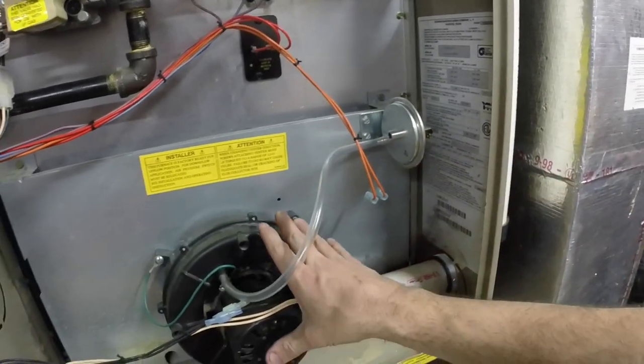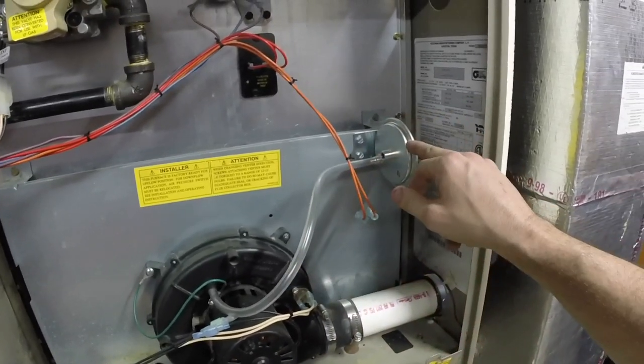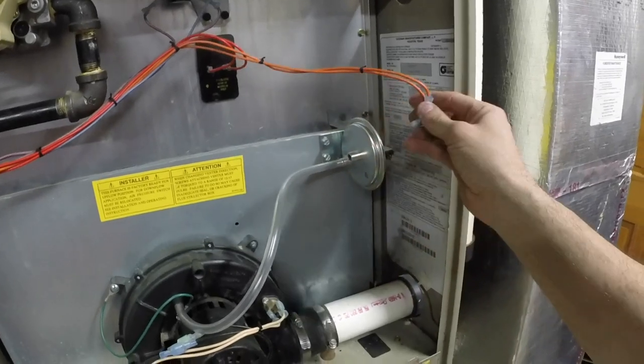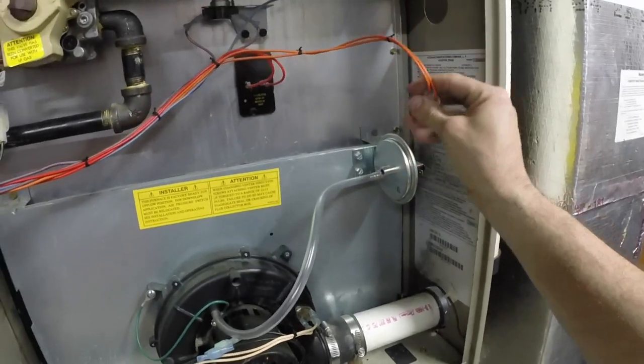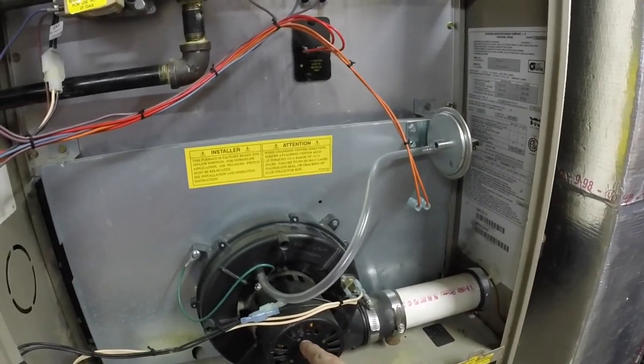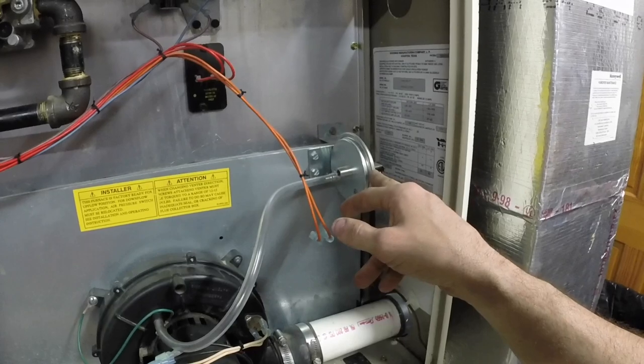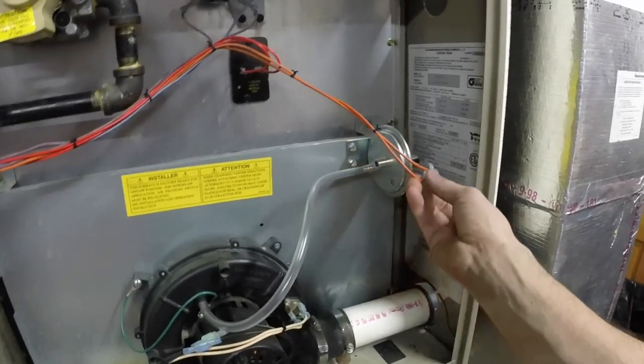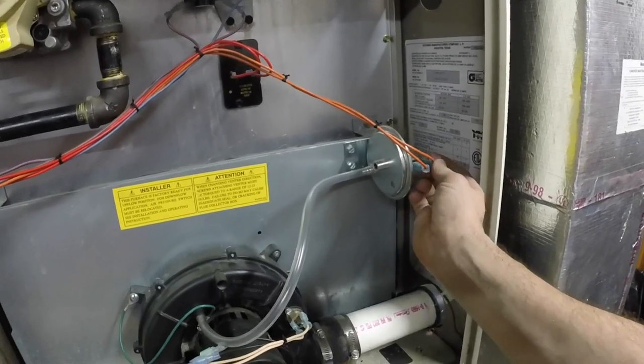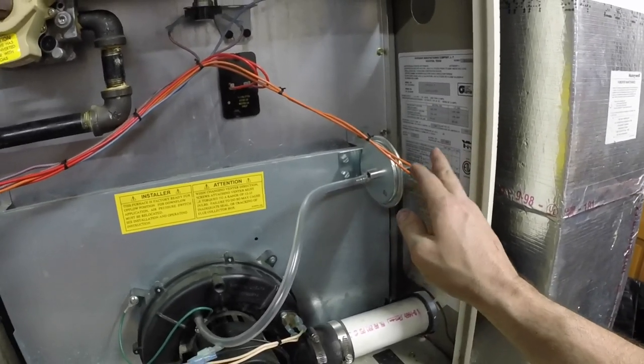If the draft inducer isn't up to snuff, it's not going to make enough pressure to click this switch, or the switch itself is bad. So you can connect the two wires off of the pressure switch, and if your furnace goes ahead and fires up, then you know the problem is the draft inducer not creating enough pressure or the pressure switch is bad. That's a real simple thing to do. It's 24 volts AC — you don't need to be scared of it. Literally connect the two wires together and figure it out.